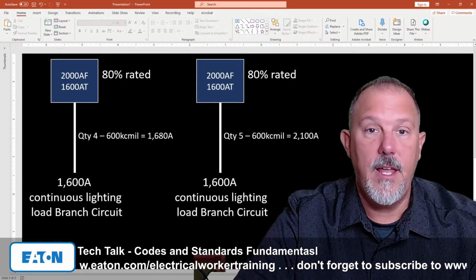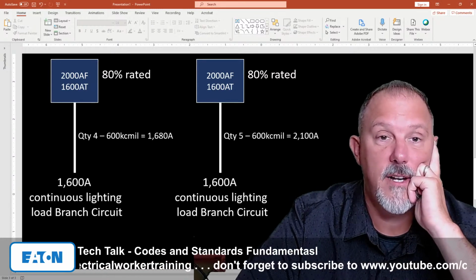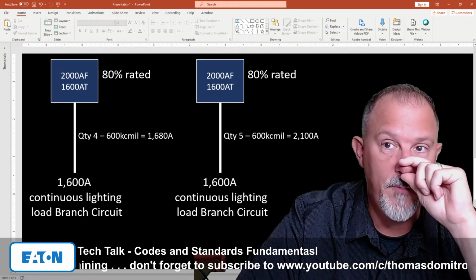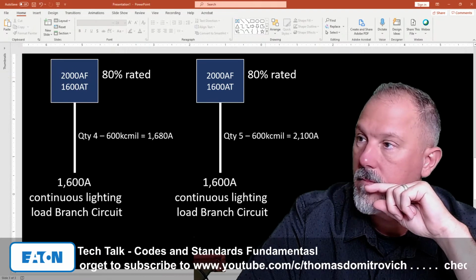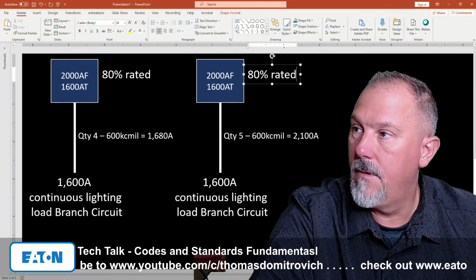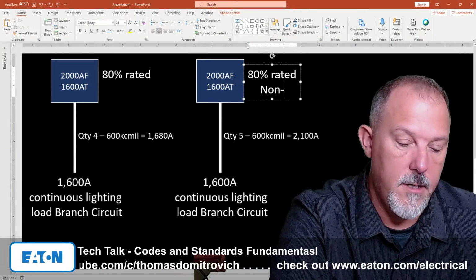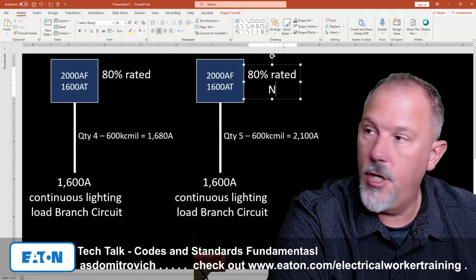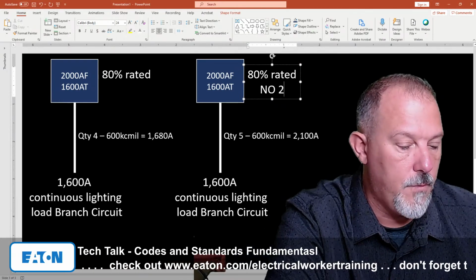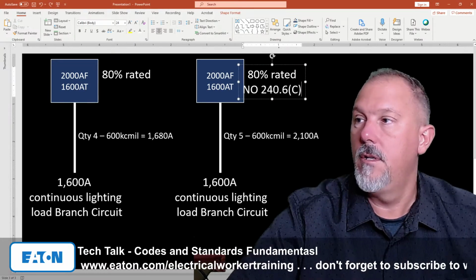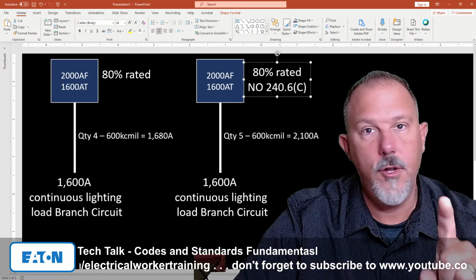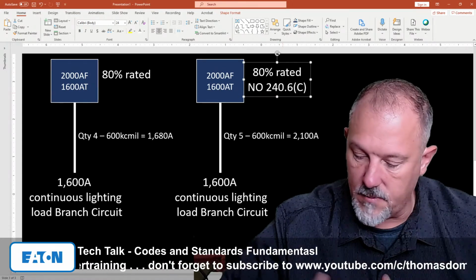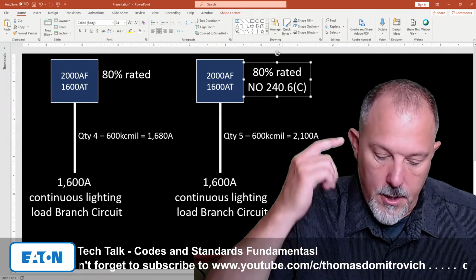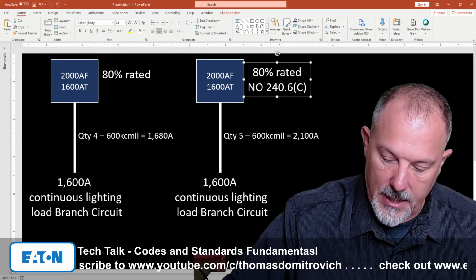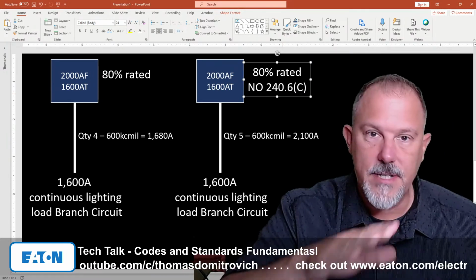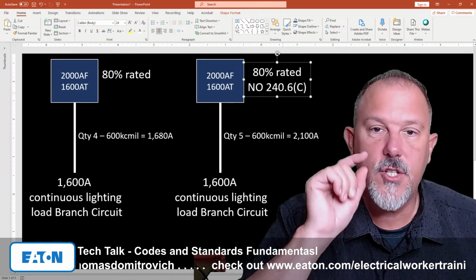So now, if I lock this cover, so this would be over here, I'm going to say no, 240.6(C), no, 240.6 Charlie. So that's an 80% rated breaker. No, you don't have 240. Let's just make sure I get my numbers right. 240.6. You don't have a 240.6(C) application. Restricted access, 240.6(C). So I don't have 240.6(C).